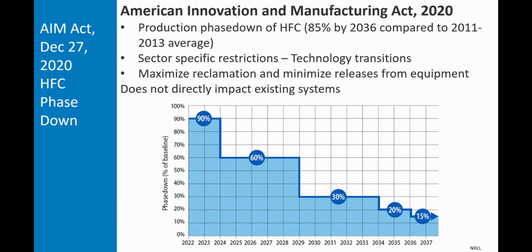So in 2036, if somebody wants to manufacture R410A refrigerant, they can do that, but they have to do it at 15% of what used to be made in 2012. So it's a pretty small amount, whereas R22 went down to almost 0.5%, which is basically zero. So the refrigerant is being phased down, as you're aware, or hopefully aware, and then the equipment that uses those refrigerants is being phased out.